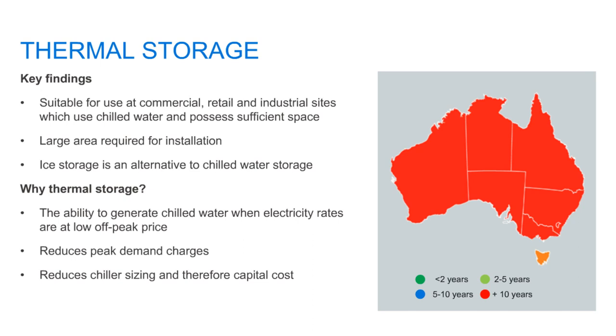The payback for this system is above 10 years, because the arbitrage cost between peak and off-peak generation of chilled water doesn't cover the capital cost of the large tanks installed. There is opportunity to reduce chiller capacity, but that's only applicable to new installs or end-of-life installs. It does give you the opportunity to reduce your peak demand charges and capital costs for new installs, and gives you a bit more capacity in the system.